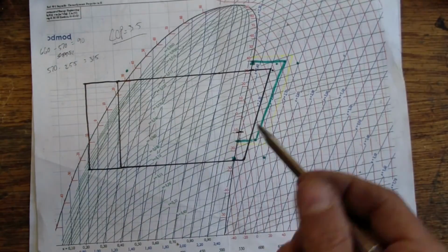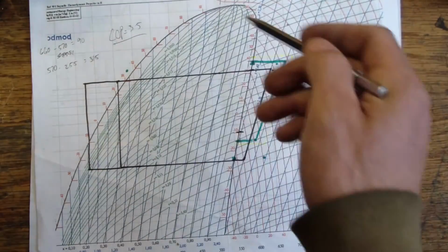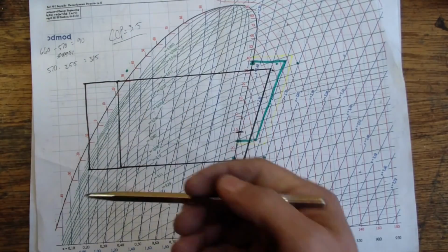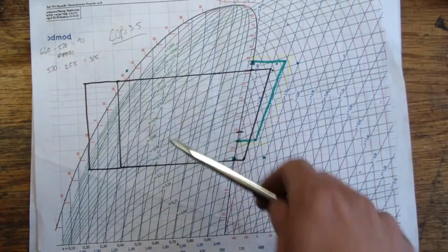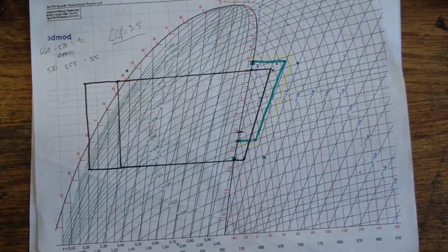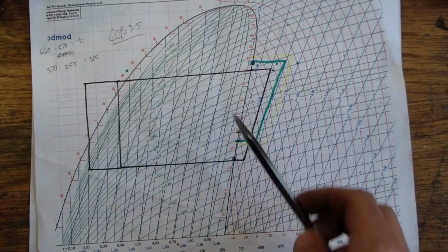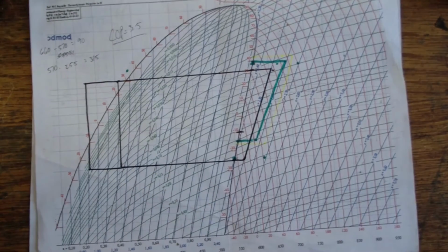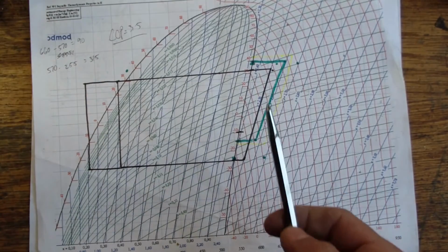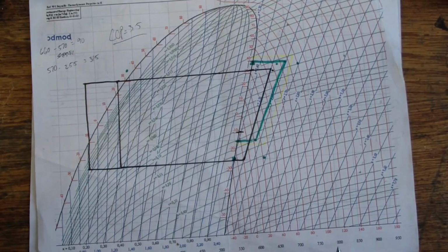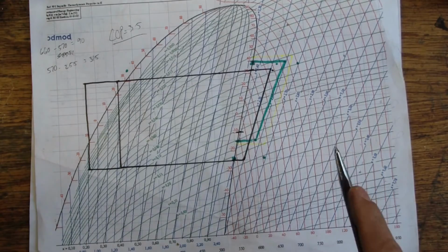And then you can get into things like blends, where they try to change the shape of this curve and develop new refrigerants that I think usually have less of a pronounced lean to the saturation curve. But with those blends, you also have slanted or sloped condensation and evaporation lines, because they're occurring across a range of pressures rather than these more or less horizontal ones here. So I don't really know where else to go with this.